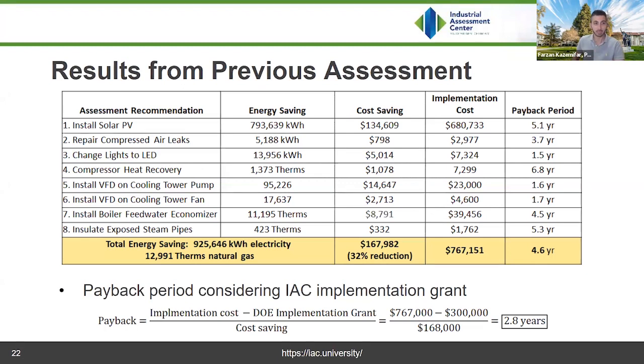Then heat recovery from the compressor, so that the use of natural gas is reduced. Installing VFDs on a cooling tower pump and fan, which results in reduction in both energy use and demand, a concern of many facilities. Using a boiler feed water economizer to help reduce natural gas use in the boiler, and also insulating exposed steam pipes to reduce heat loss and natural gas use.